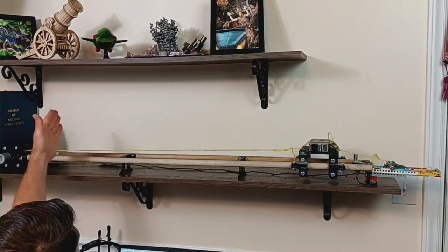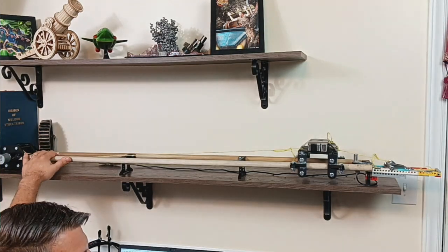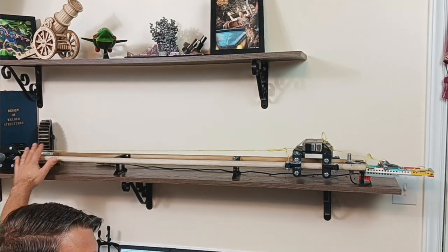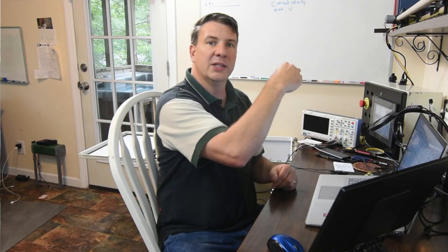So I want to make sure that my high 1 and high 2 are active, reading as a check, and then it's going to go all the way back and do that. So that's 2 stages. Stage 1 is moving this way till I hit both of the highs. Once I get both of those, I'm going to go to stage 2 and move it all the way back. So when I'm in one of those 2 stages, I can't be doing other things. I can't be moving forward and backwards at the same time.